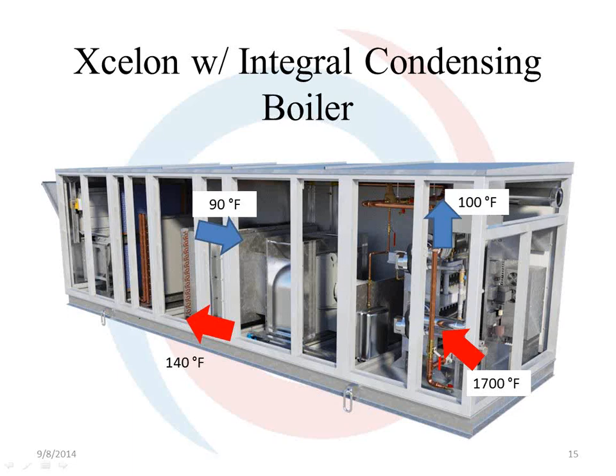While the flue gas still has a large delta T, the delta T of the propylene glycol loop is only 50 degrees. This is what allows the unit to maintain that discharge temperature of plus or minus 0.5 degrees. So this high temperature difference allows the boilers to maintain their efficiency. All we do is change this delta T here to satisfy the discharge air temperature.